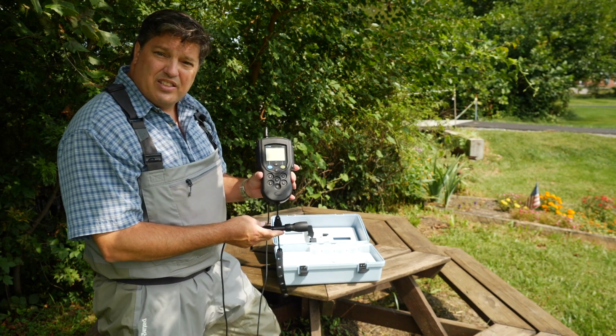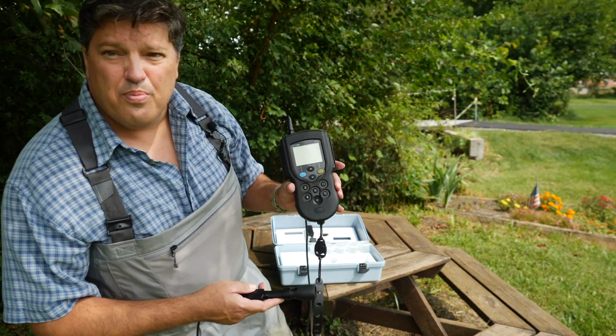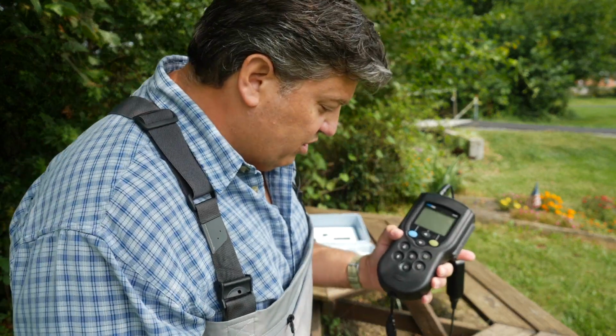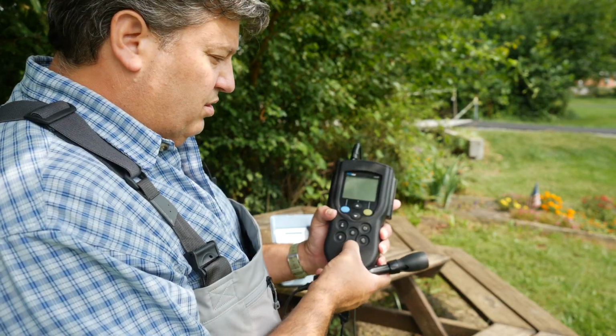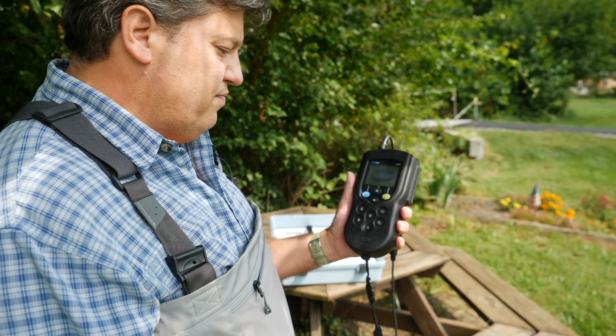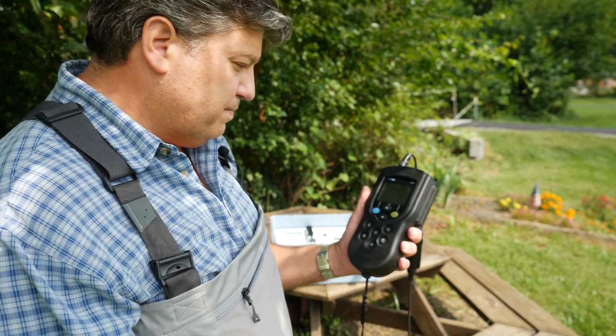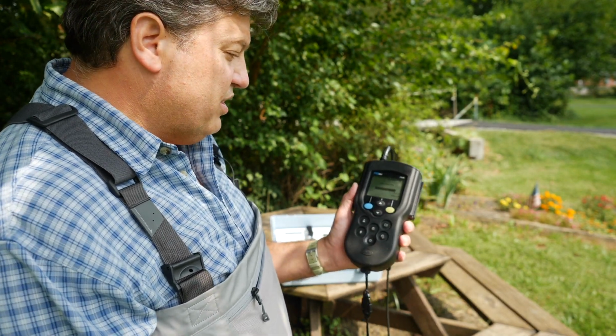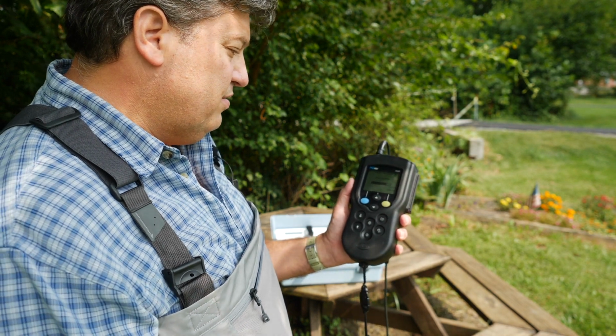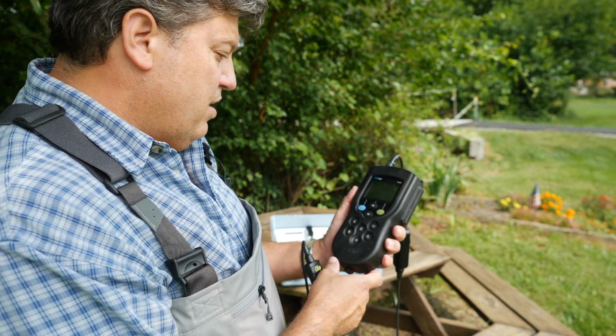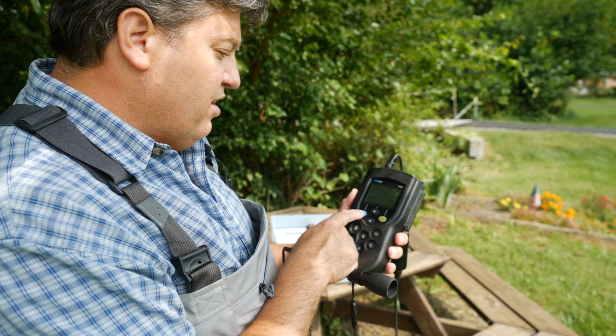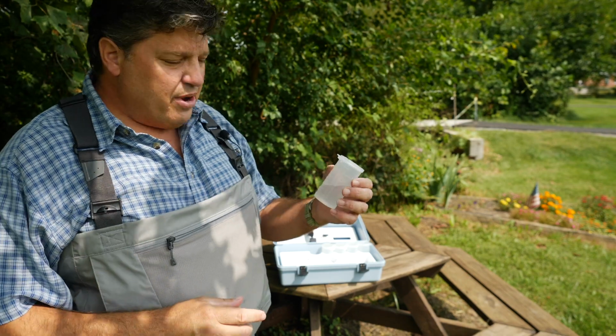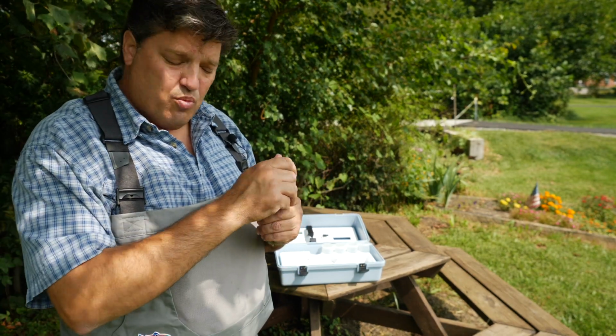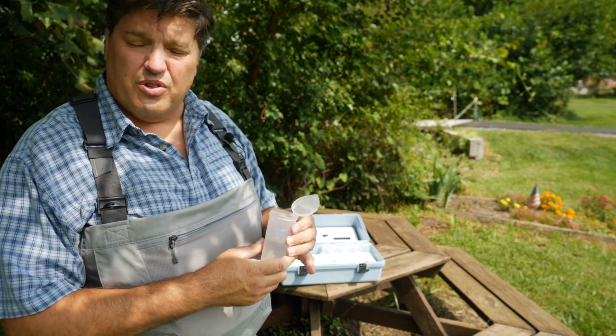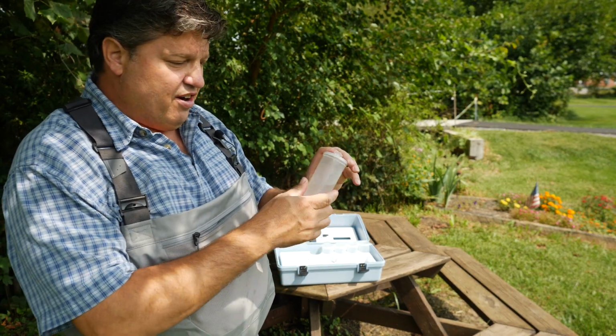There are a couple buttons here on the meter, and we're just going to turn on the power button and get it set up here. So notice it's checking for the probe connection. It's connected, and then in this case we can calibrate the sensor. To calibrate the probe, we're going to saturate some water. I just filled this up with some water. It's got about half air in it.